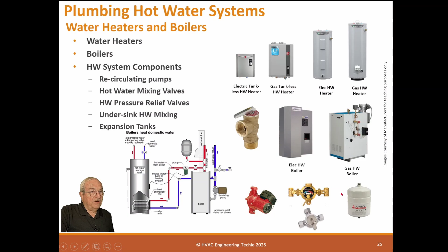And then we have under sink hot water mixing valves. What we do here under sink, we put in this manual valve under there, and you adjust it to make sure you get the temperature you want. And it will always mix the water at the sink level. These are used in commercial bathrooms or whatever, that mix the hot water and cold water together so we don't get a scalding situation on a person. And the expansion tanks for any time we have a hot water heater, because cold water or hot water does expansion, so they put those in there.